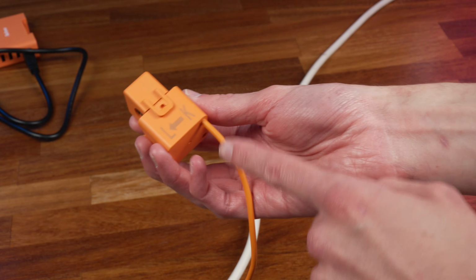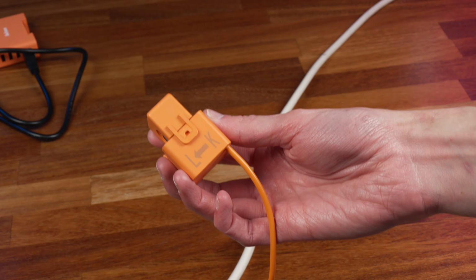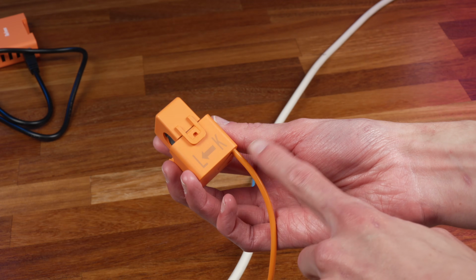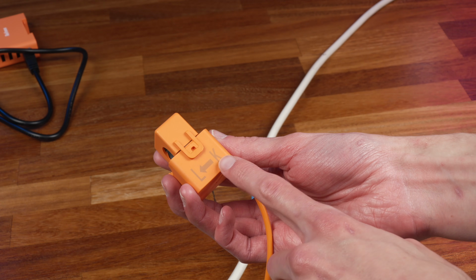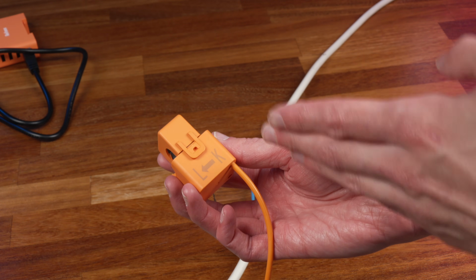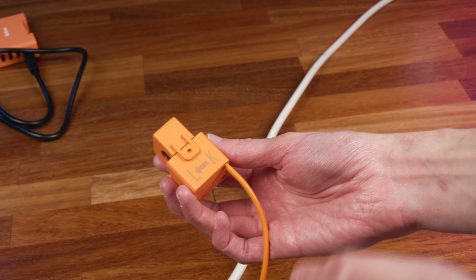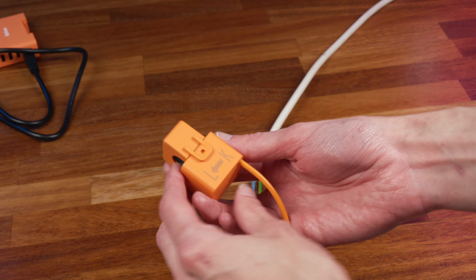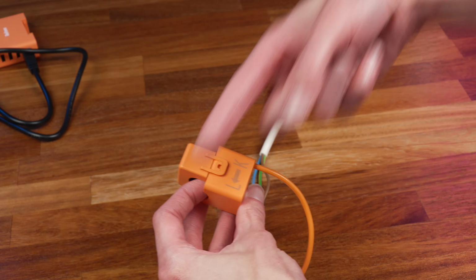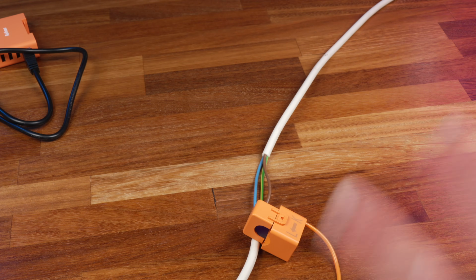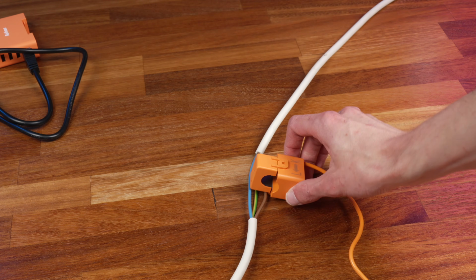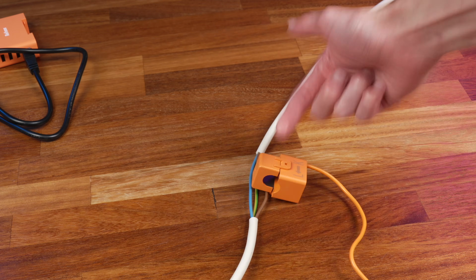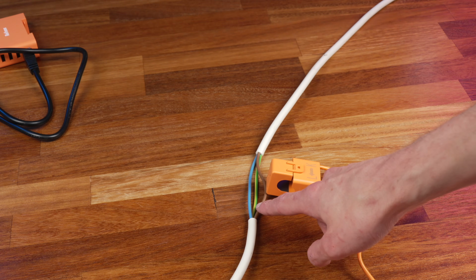And the final thing to note when you're installing these CTs is you have to install them in the direction of the current flow. On these ones here, it's labelled with these letters K and L with an arrow in between them. You should normally install these so that the arrow points in the direction of current flow. So this arrow should point away from the power supply and towards the load. So for this test setup here, you'd want the arrow pointing away from the socket and towards the device we're wanting to measure if we're putting it on the line conductor.